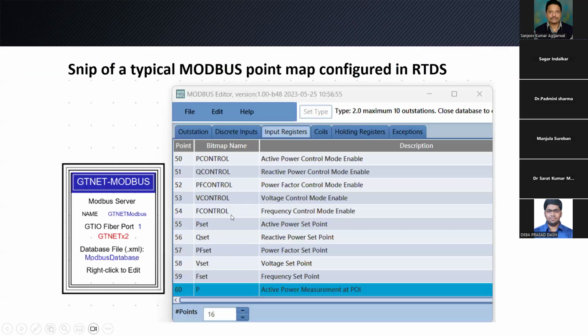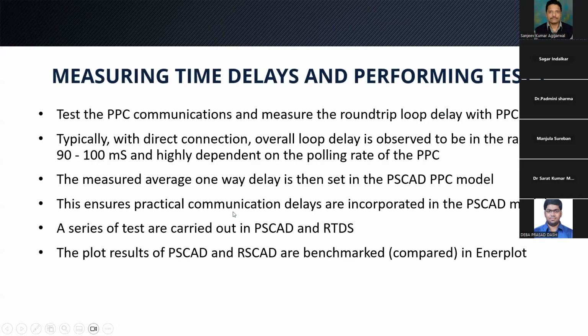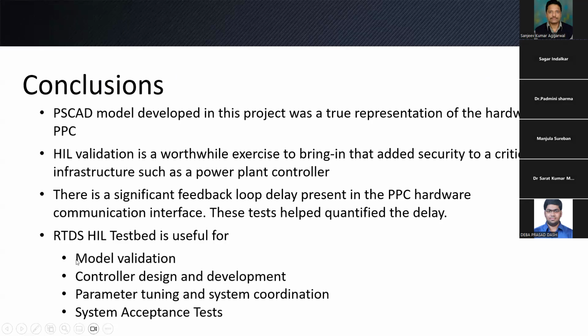When this is taken care of, when Modbus mapping is performed, we send a command to the device and read the output of it. Through this method, we measure the delay. Typically, what we saw is that the delay is between 90 to 100 milliseconds. It depends on the polling rate of the PPC and the devices between the PPC and the receiving devices. That will be measured and modeled, and then we'll compare the two together. Okay. This way, we can generate a report and confirm that the model developed in PSCAD is a true representation of what you have in the physical controller.